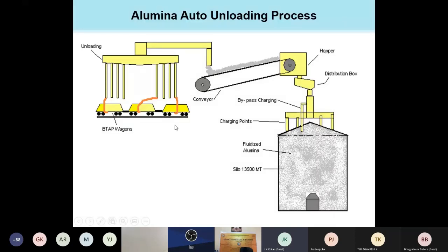Then air fluidizes the alumina powder, and it falls onto the conveyor belt, and the conveyor belt takes the alumina powder to the respective silos. So this program is written within the PLCs. If the valve running indication is not coming, then the conveyor belt will not run, because it is interlocked.